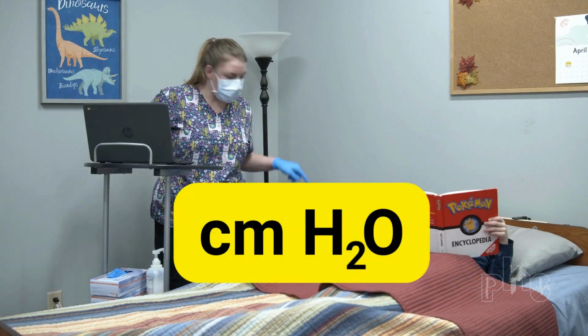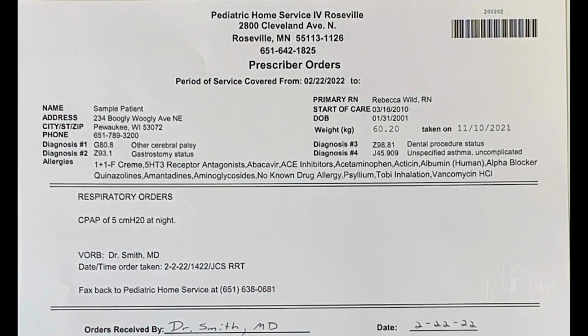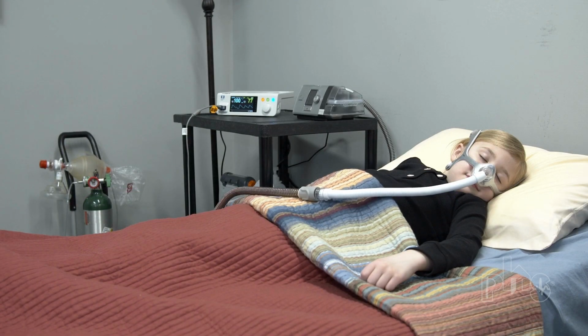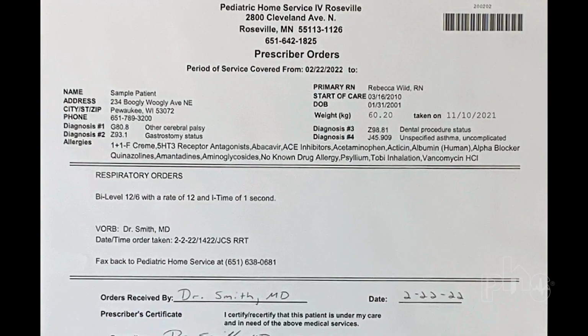CPAP and BiPAP pressures are measured in centimeters of water and are prescribed by a physician. Patients using CPAP generally have prescriptions with only one pressure setting. An example of a prescription is CPAP of 5 centimeters of water at night. Patients using BiPAP have two prescribed pressure settings, IPAP and EPAP. An example of a BiPAP prescription is IPAP of 12 centimeters of water and EPAP of 6 centimeters of water, or BiPAP of 12/6. The prescription may also include a breath rate and inspiratory time, or I time, which is the amount of time the IPAP is delivered.